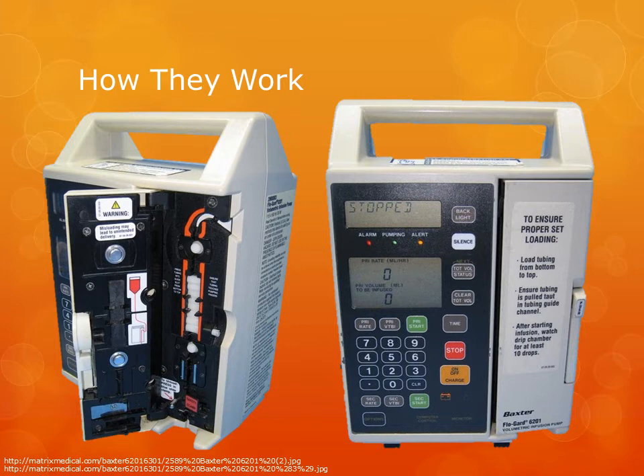In addition to this, the system's got several safeties on it. For example, if you get a bubble into the line, it's very bad if this makes it into the body. So there are actually sensors on this device that will sense for that and give an alarm. In addition to this is an occlusion, which is actually a pinch of the line where no more fluid is flowing. This will also give an alarm so that the patient or the nurse will know that the device is not administering the medication or whatever other fluid is being injected properly.